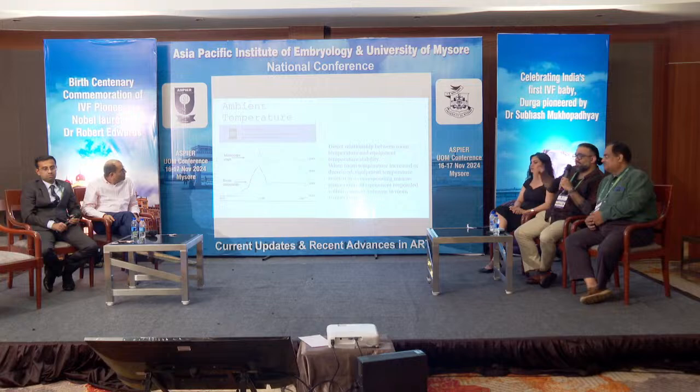That obviously takes care of the majority of the things. But it's always better to have another VOC device inside your lab, because every time you walk in, you are carrying along a lot of VOCs. So that does not get fully filtered. Everything that you're opening up inside the lab is also producing VOCs. So if you're having a good AHU, it's always better to have an additional small meter inside the lab. That's what we have always been doing.